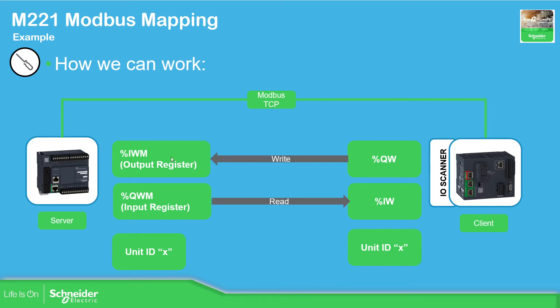The %IWM area is called the output register — output meaning from the other side. All the information is coming from the other side, and I write it from the M262 into the M221. The %QWM, which would be the input register, is for reading from the other side. It's a little confusing now, but when we go into both software tools we can see the difference.